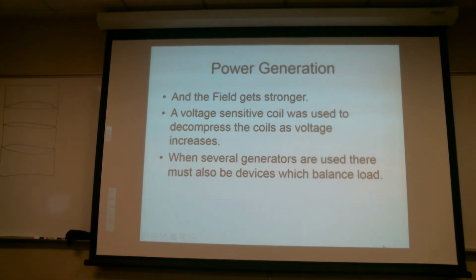Then, of course, we had to add another couple of things in the circuit. One was we needed a way to adjust this thing a little bit in the field. It turns out just about every voltage regulator out there has a way to adjust it, though it's not necessarily meant to be field adjustable. But these had to be field adjustable because they were installed on bigger units that typically had multiple engines with multiple generators, and we needed to make sure each generator is operating at about the same output. Otherwise, we're going to get one generator motoring the other generator, so we have to be careful to prevent that.